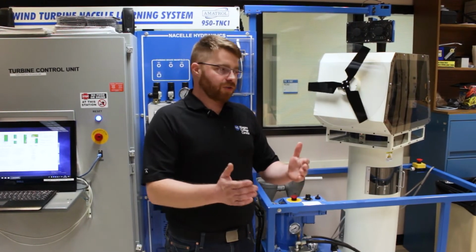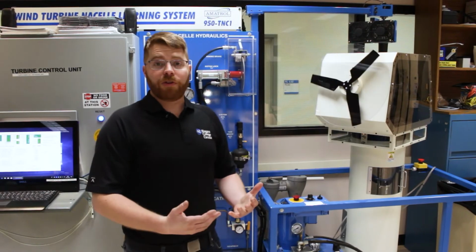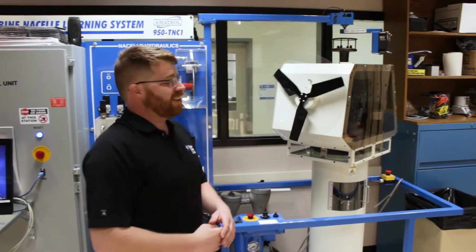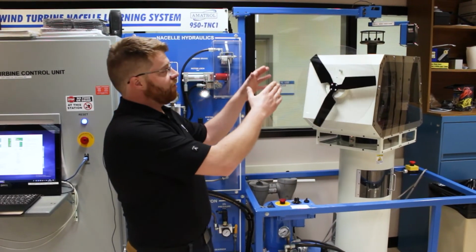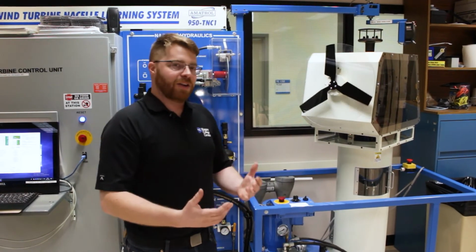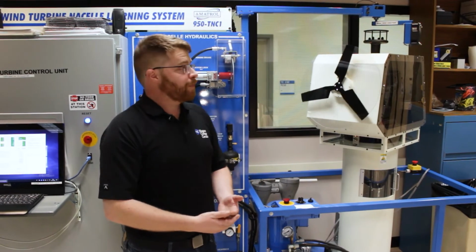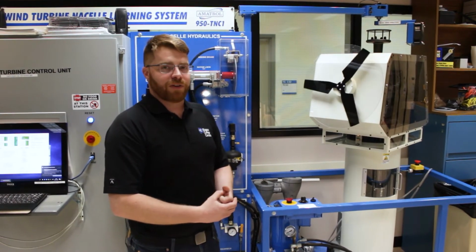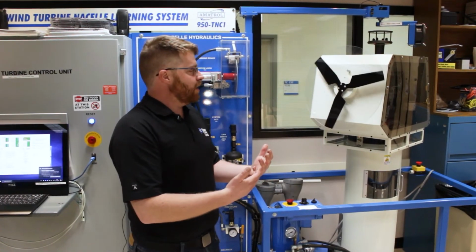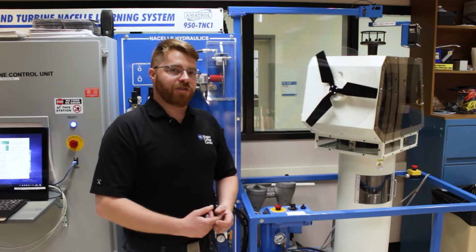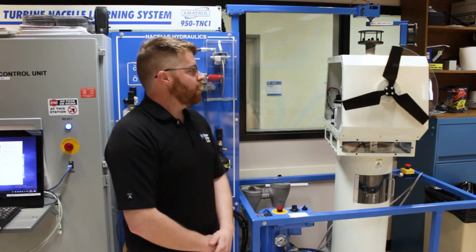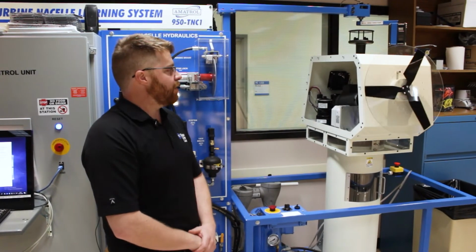And that's called yaw. The direction which the wind turbine will face should always be into the wind. So if I make a simple adjustment to my simulated wind speed, there's a device up on top of this simulated nacelle called an ultrasonic anemometer, and it is measuring both the wind speed and the direction. By changing the direction that the wind is coming from, that feedback loop processes the change in information, and the turbine controller will make an adjustment to the yaw position and cause the nacelle to line up with the wind direction. And that's what you see happening beside me at this very moment.